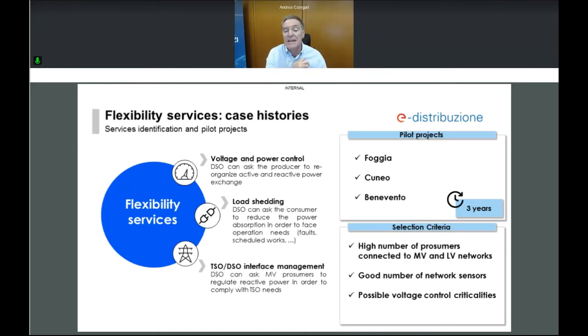For this purpose, E-Distribuzione is working to set up and run three pilot projects that will last three years in three Italian areas: Foggia, Benevento, and Cuneo. These areas have been chosen because of the distributed generation, and at the same time, the operation is already integrated with a large number of sensors and communication technologies. Moreover, according to estimation and simulation, in these areas voltage control for LV customers can become critical and can require a DSO solution to ensure compliance with technical standards.